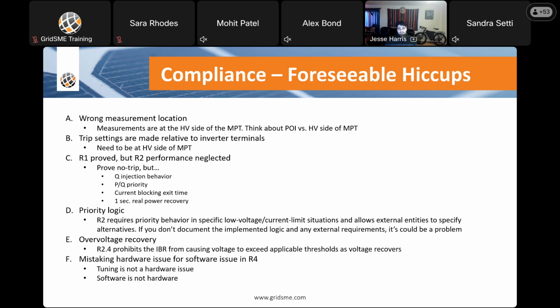Requirement 1 is proved, right? So you prove that you ride through, but what about your PQ priority? What about your current blocking exit time if you hit that really low voltage? What about recovering your real power within 1 second? And then Q injection behavior if you're in Q priority. Well, those are all under R2, so you can have R1, but R2 can fail. And you need to be sure that you prove that it passes that requirement.